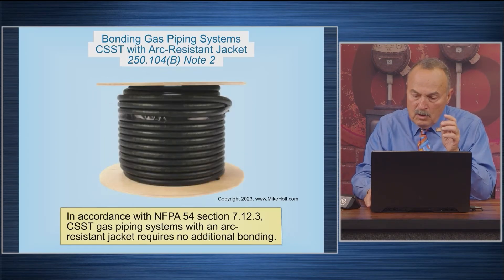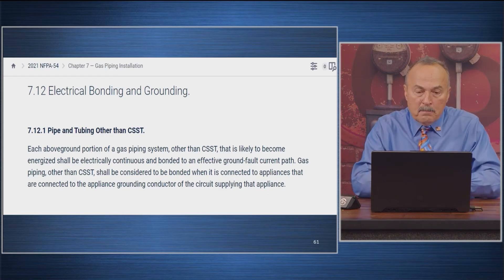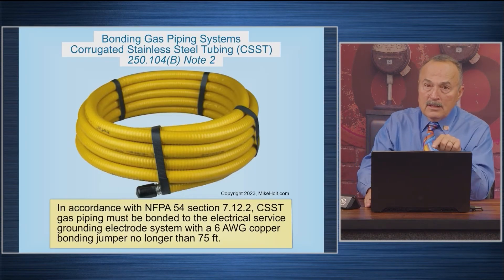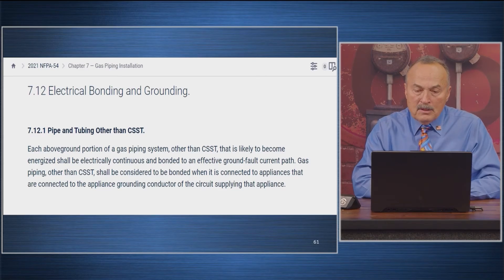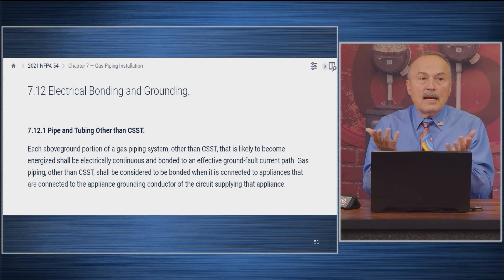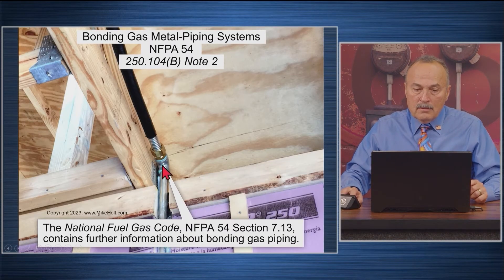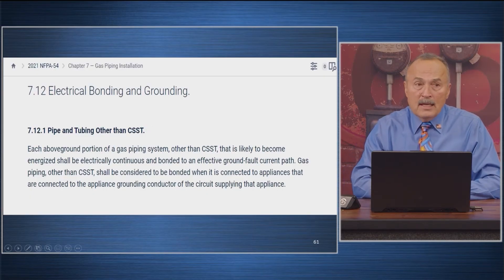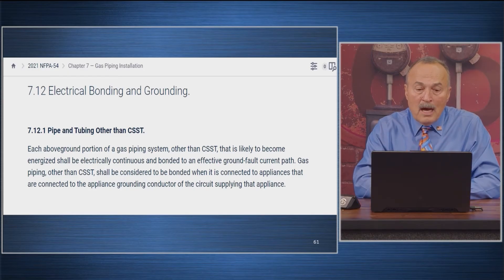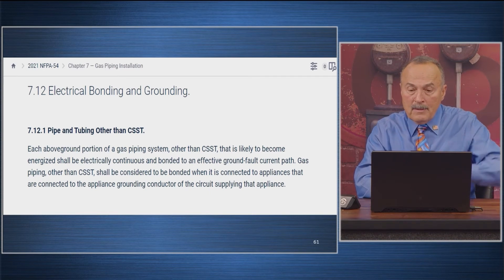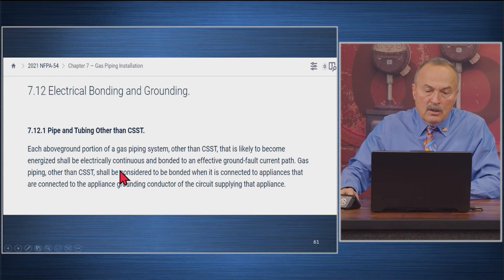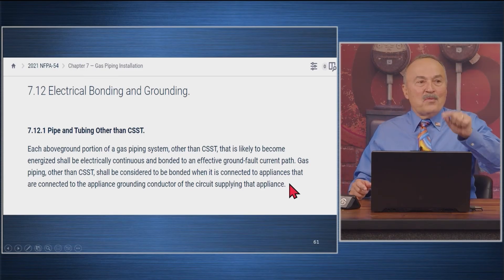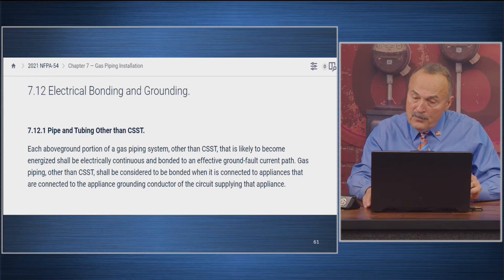NFPA 54 7.12.1 states: above-ground portions of gas piping systems other than corrugated stainless steel — such as black iron — that are likely to become energized, such as connected to a dryer or range, shall be electrically continuous and bonded to an effective ground-fault current path. Gas piping other than corrugated stainless steel shall be considered bonded when connected to appliances that are connected to the appliance equipment grounding conductor of the circuit — exactly what the NEC says.